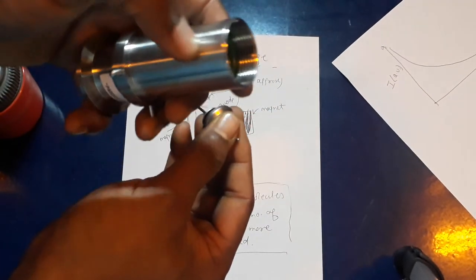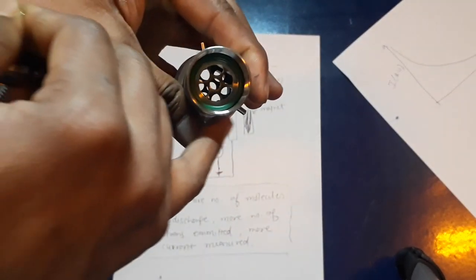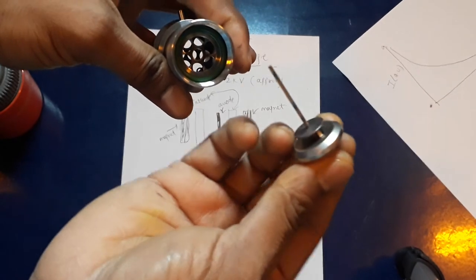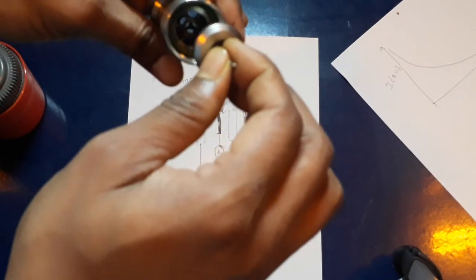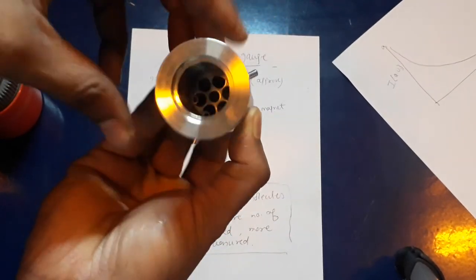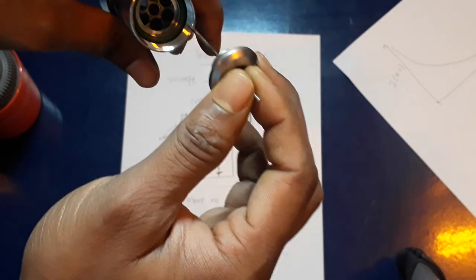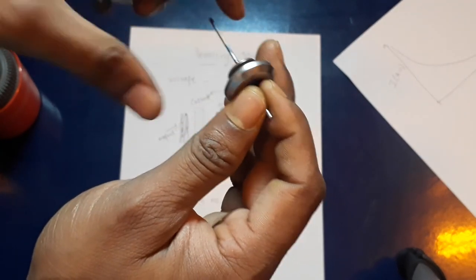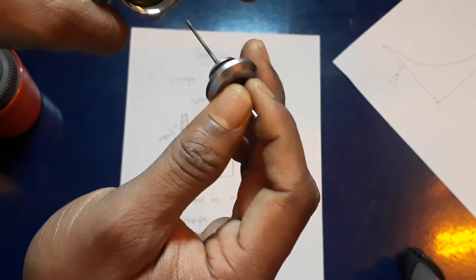This o-ring makes sure that the design is such that it is leak-tight. From the backside you can tighten and it will be leak-tight from the backside. The very high acceleration voltage is applied between this body and the anode, so there will be discharge between this body and the anode.